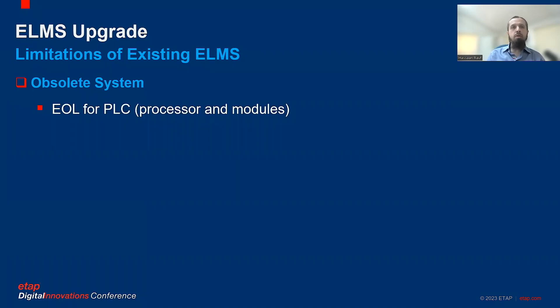So now looking at the need of upgrade, or the limitations of the existing ELMS, which forced us to go for this upgrade. The first and foremost was obsolescence. We were having an obsolete system. It was an Allen Bradley PLC 5/40E, and most of the modules were obsoleted a long time ago, and we were having real difficulty in getting reliable or new spares for this system. So the reliability of the system was at stake.